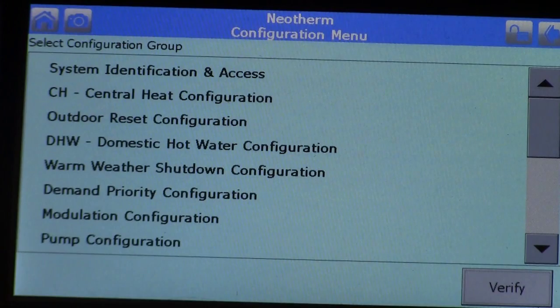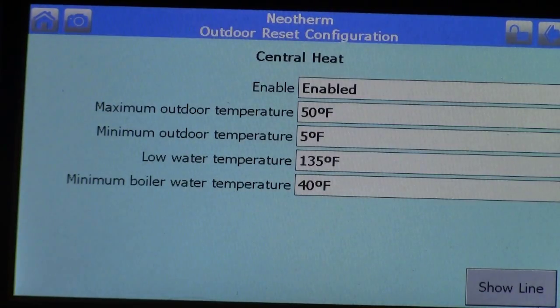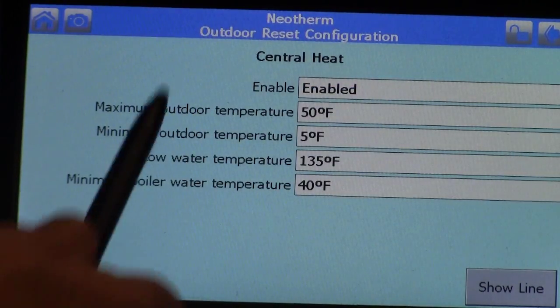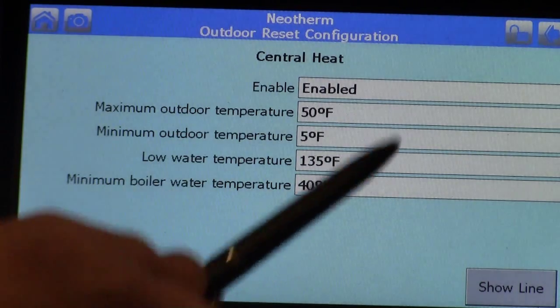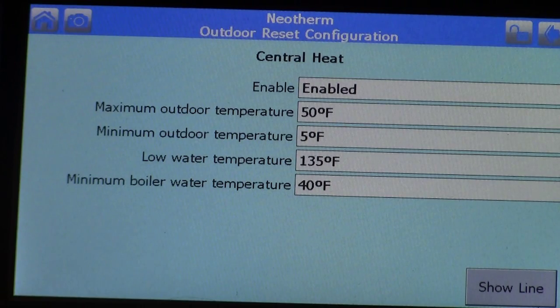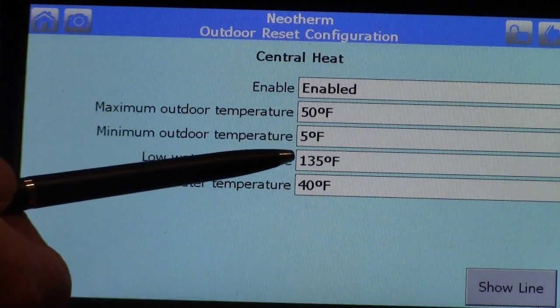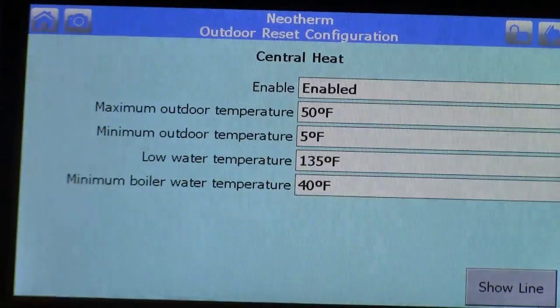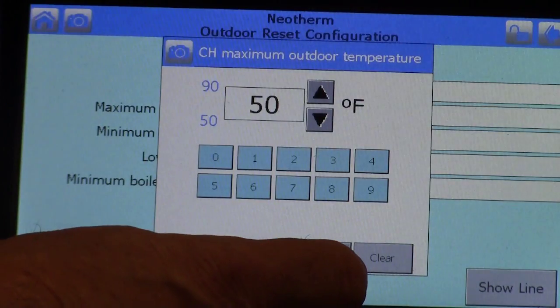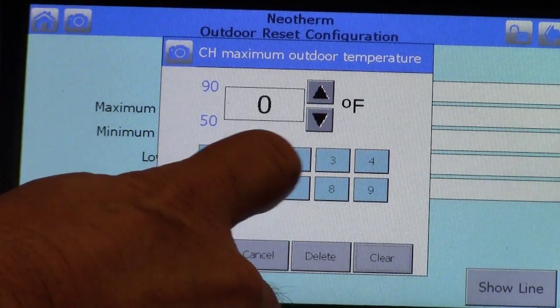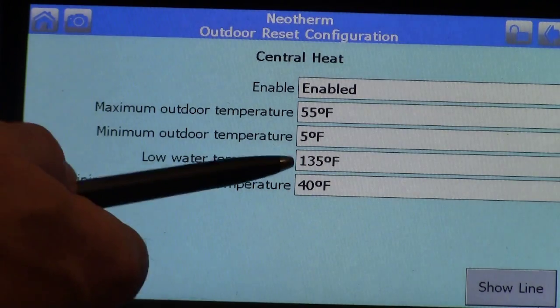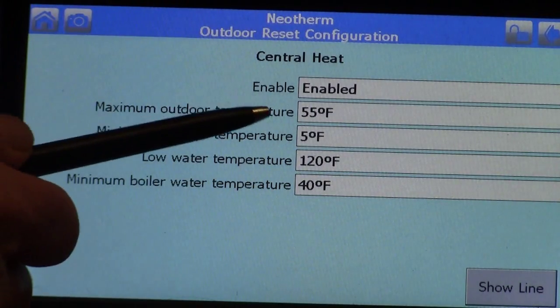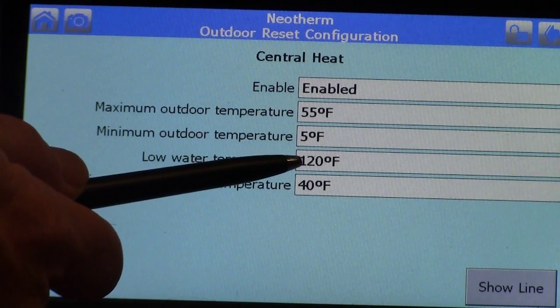Hit the back arrow and come down to choose outdoor reset. Outdoor reset should be enabled — if not, click on it and enable it. Now we're going to set our temperatures. The max outdoor temperature corresponds with our low water temperature. For example, on a 50 or 60 degree day, maybe we only need to supply 135 degrees or lower. For this fan coil example, we'll say the low temp is 120 degrees at roughly 55 degrees outdoor air. Go in, set 55 degrees, click OK, then set the low water temperature to 120, click OK. So anything above 55 degrees of outdoor air, we're only going to deliver 120 degrees.